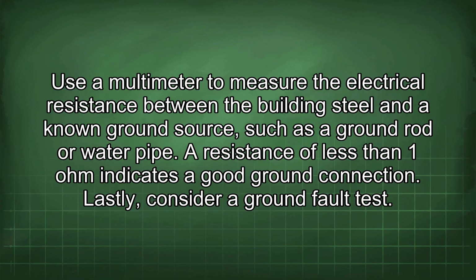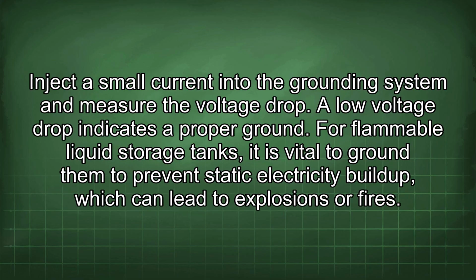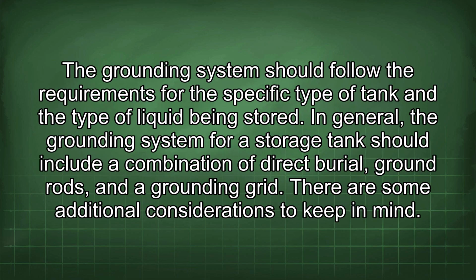Lastly, consider a ground fault test. Inject a small current into the grounding system and measure the voltage drop. A low voltage drop indicates a proper ground. For flammable liquid storage tanks, it is vital to ground them to prevent static electricity buildup, which can lead to explosions or fires. The grounding system should follow the requirements for the specific type of tank and the type of liquid being stored. In general, the grounding system for a storage tank should include a combination of direct burial, ground rods, and a grounding grid.